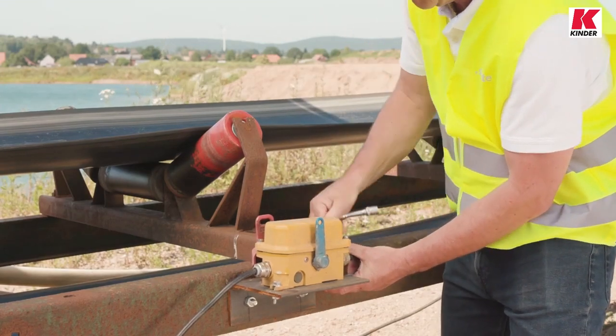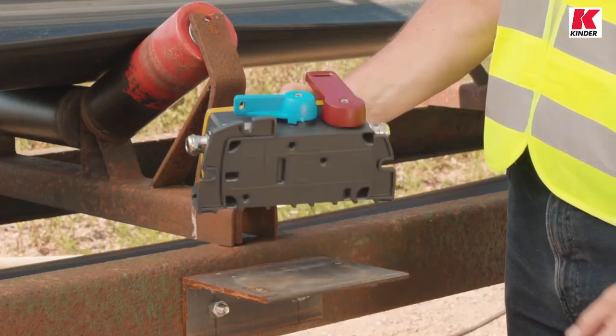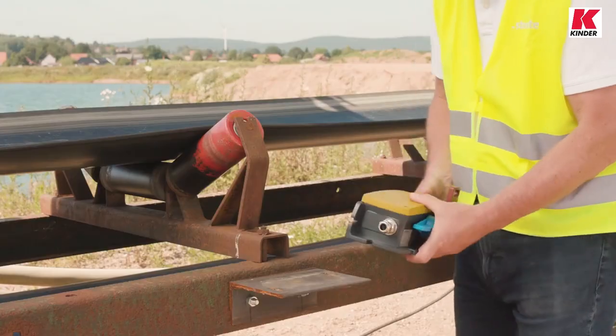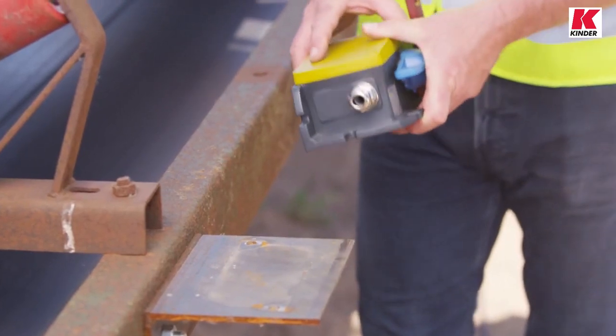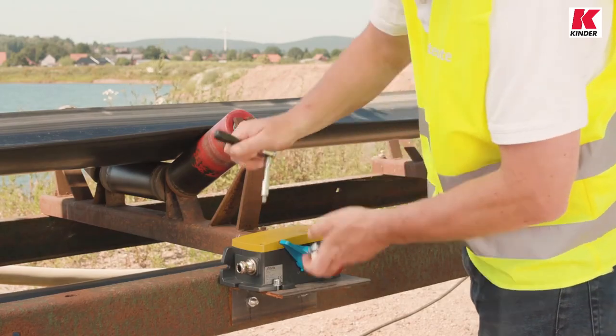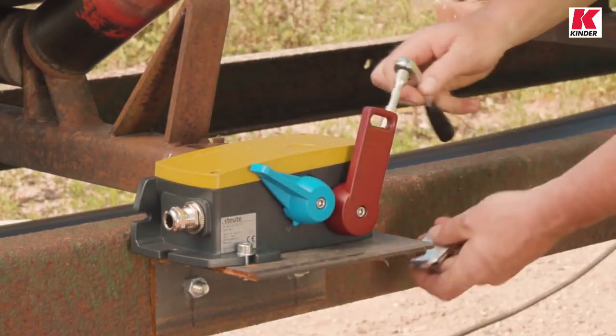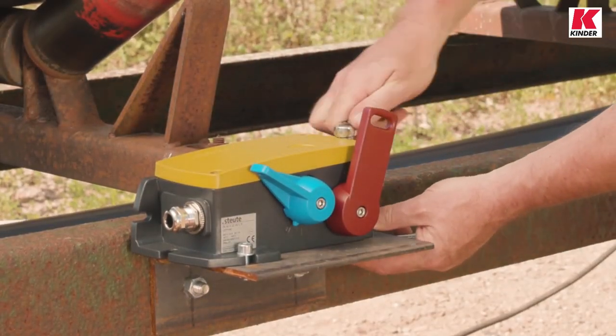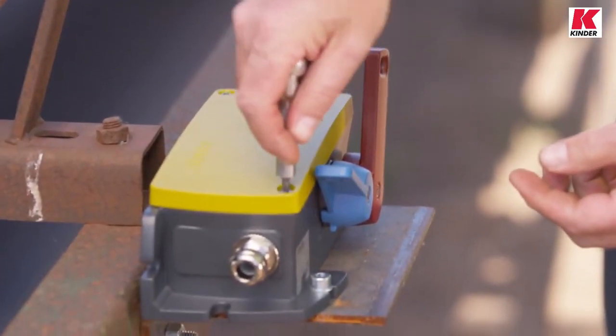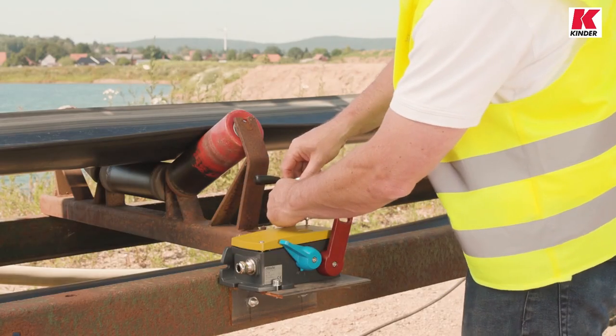Simply unscrew the old switch and attach the new one using the same fixing points. The steute ZS92S can be mounted in any position. Of particular interest, it has several different base and rear fixing points, all set at the same distances as the most popular competitor products on the market. This means that defect competitor switches can usually be replaced with steute switches without having to change their location. In addition, both the red trip lever and the blue reset lever of the ZS92S are available with mounting to the front or to the rear, making the ZS92S one of the most flexible pull wire switches in the marketplace.